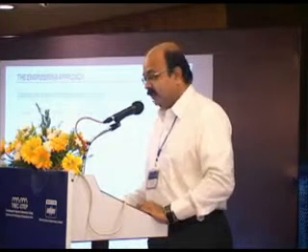And then you have to also understand what kind of margins were there in the original material. Where have you operated the unit with respect to what margins you have, because of the stress it went through. And that will clearly tell if the yield strength is so much and you are far, far below, you are fine. That material is going to withstand a few more years.